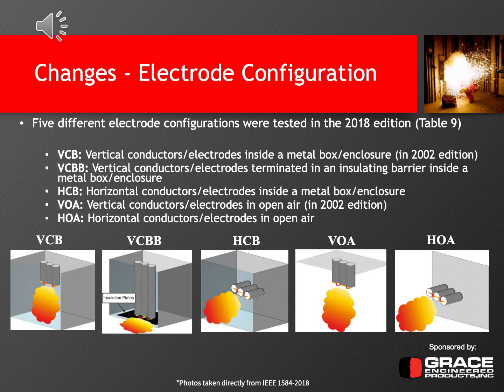So next, one of the major changes and actual additions is the electrode configuration. In 2018, there are 5 different electrode configurations that were tested. It's also known as Table 9 in IEEE 1584 2018. And of these 5 electrode configurations, the first one is VCB, which is vertical conductors or electrodes inside a metal box or enclosure. And VCB was included in the 2002 edition.